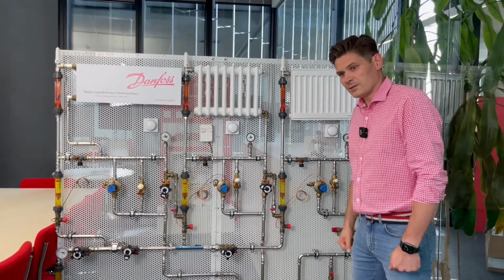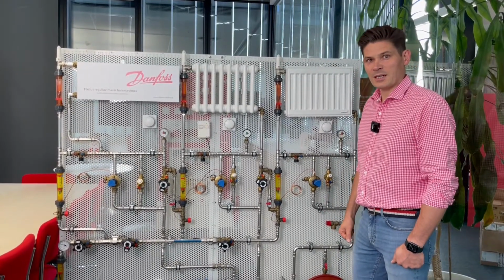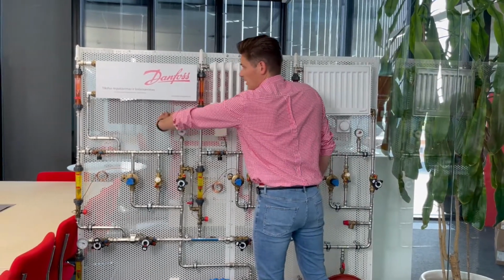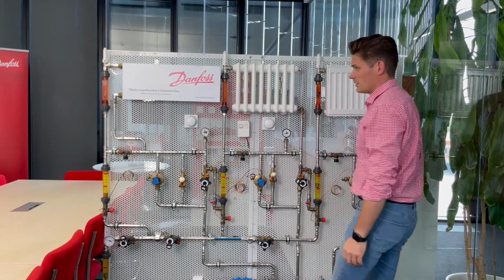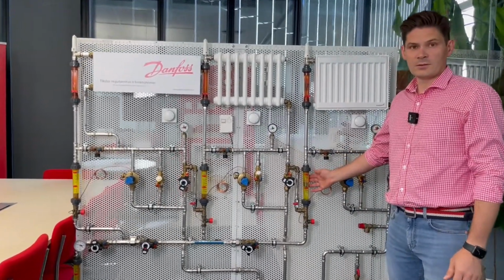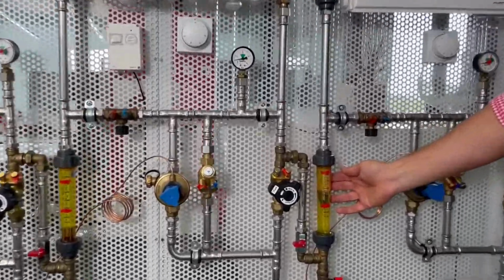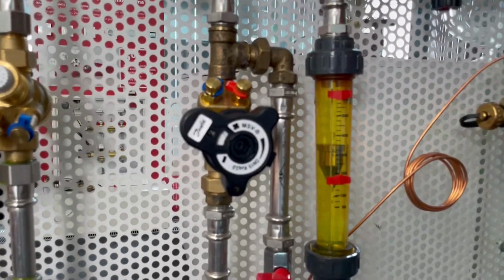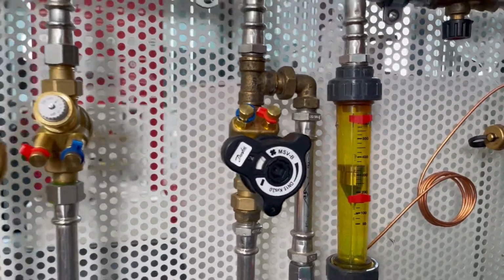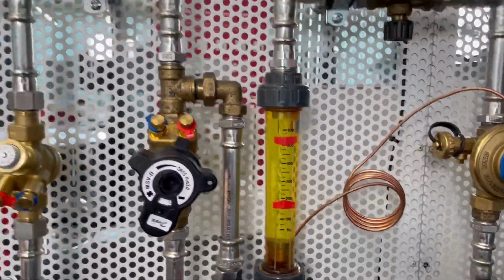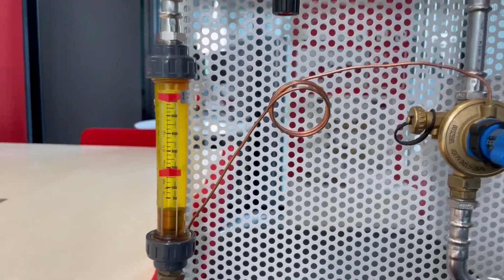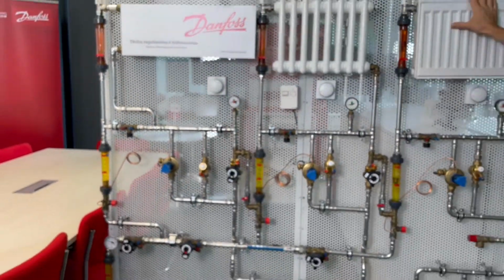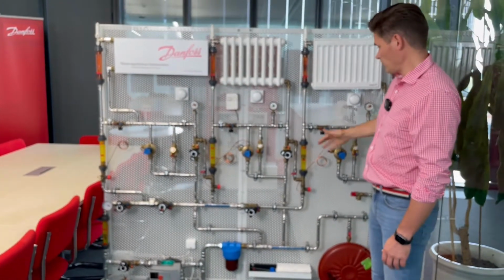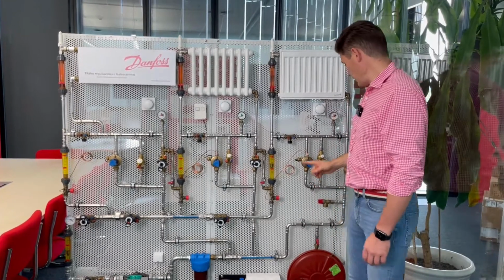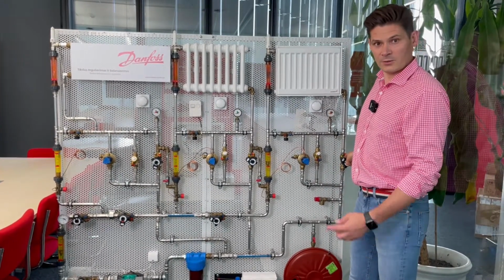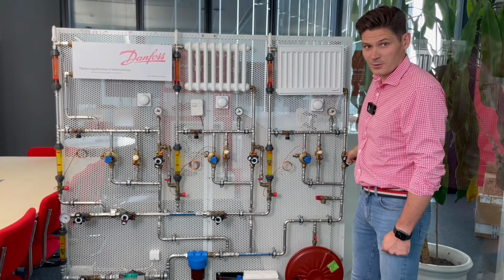But unfortunately, the sun comes again in springtime and heats half of the building, and half of the building doesn't need heating. And again, we have overflow on the risers on the north side that still need heating. Again they have noise, and again they call the maintenance company. The maintenance company comes and sees that, oh my God, we already came here 2 times. Once it was too much, then it was too low flow. Now again we have too much flow. They know that if they regulate this manual balancing valve, they will need to come again the next day or after 2 days.